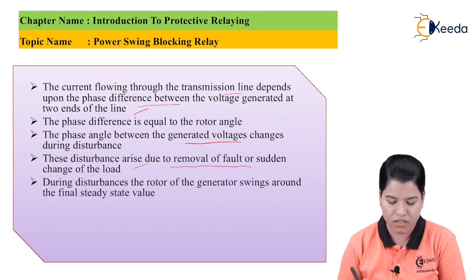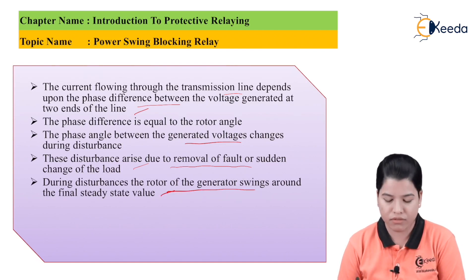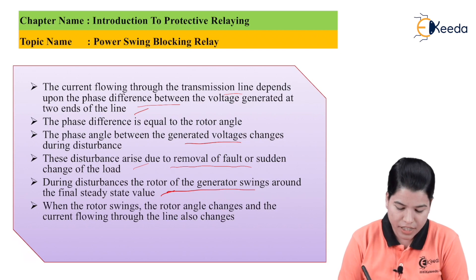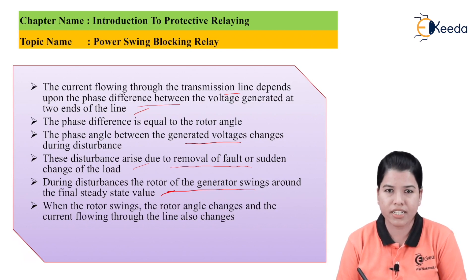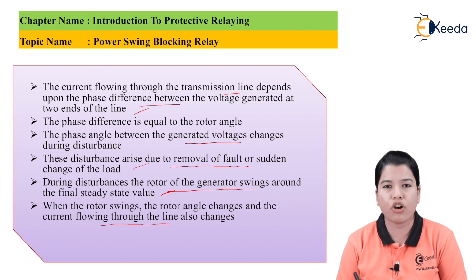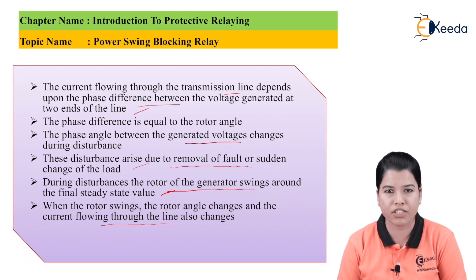During the disturbances, the rotor of the generator will swing around the final steady-state value. When the rotor swings during the power swing condition, the rotor angle changes and as a result, the current flowing through the line also changes. This is because the current flowing through the line depends upon the phase difference between the generated voltages at the sending-end generator and the receiving-end generator, which itself depends upon the rotor angle.